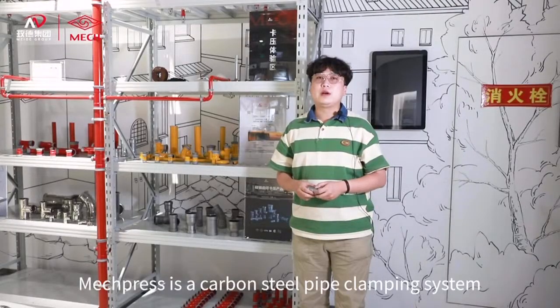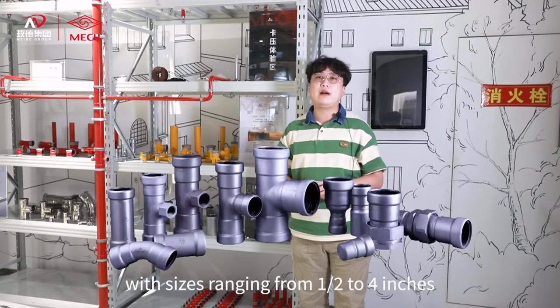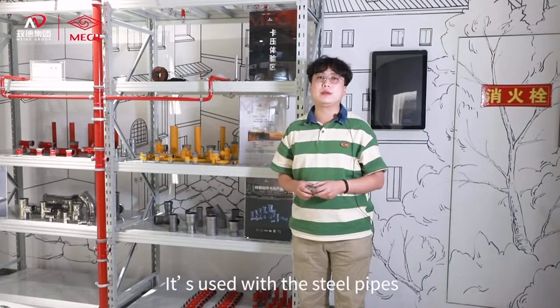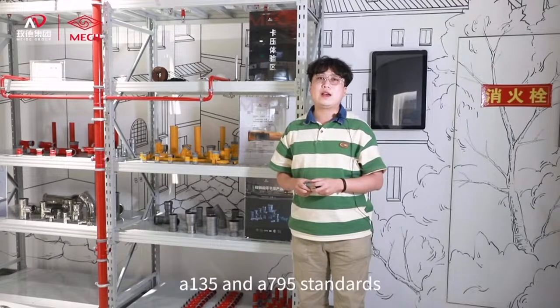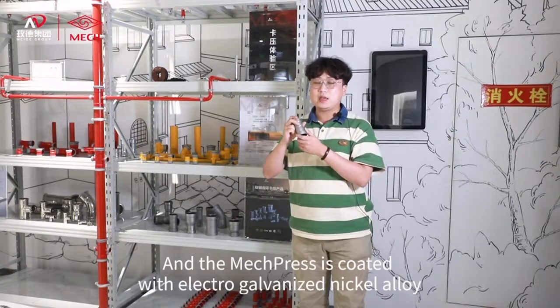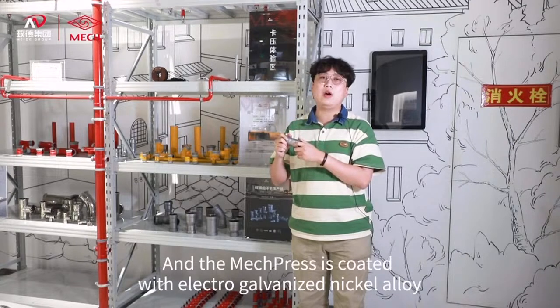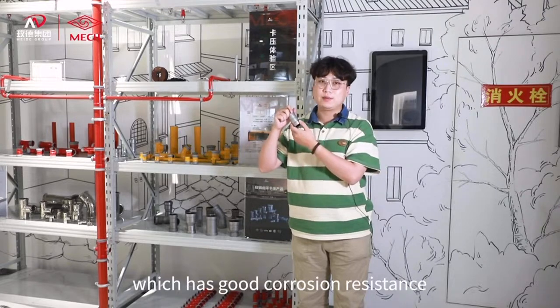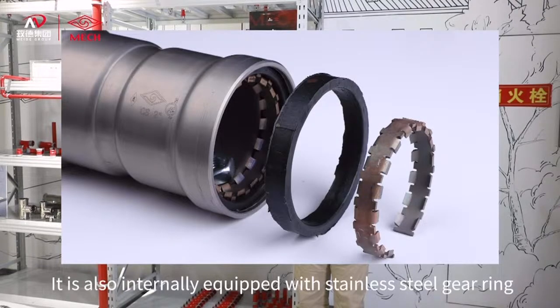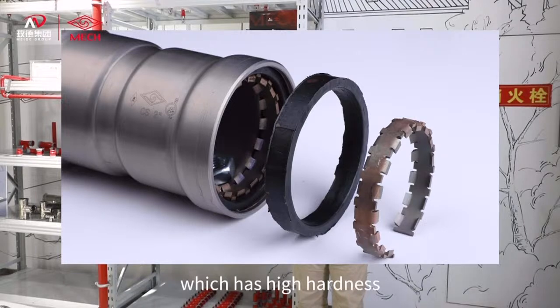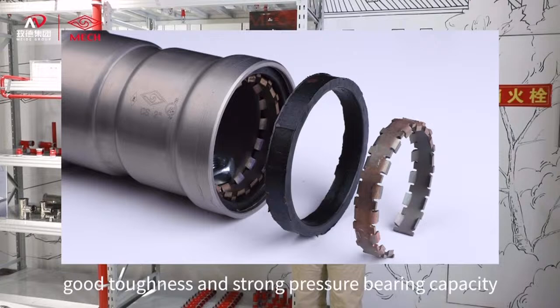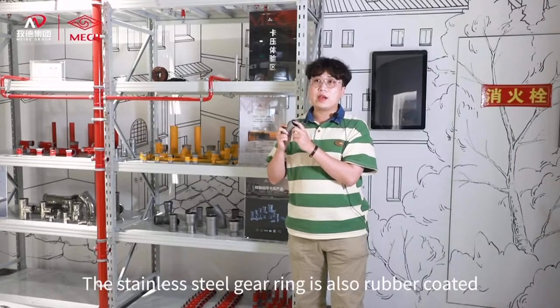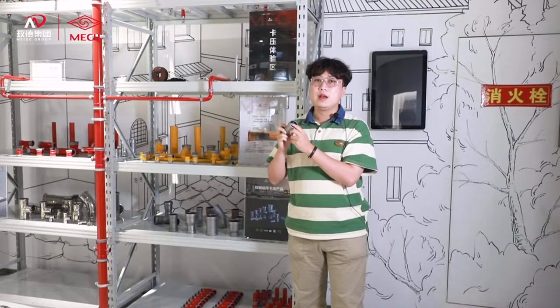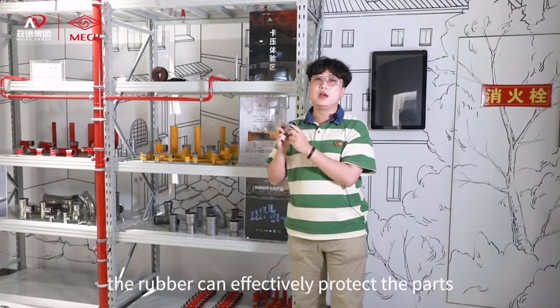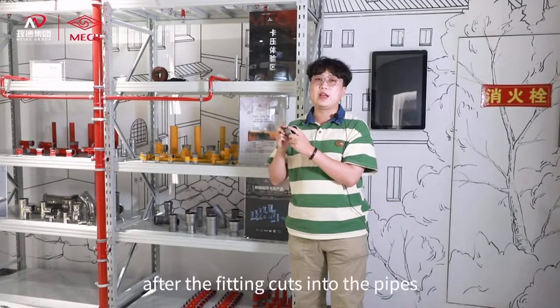MechPress is a carbon steel pipe clamping system with sizes ranging from half to 4 inches. It is used with steel pipes complying with ASTM 53, 106, 135, and 795 standards. MechPress is coated with electro-galvanized nickel alloy, which has very good corrosion resistance. It is also internally equipped with a stainless steel gear ring, which has high hardness, good toughness, and strong bearing capacity. The stainless steel gear is also rubber coated. The rubber can effectively protect the parts where the coating is damaged after the fitting cuts into the pipes.